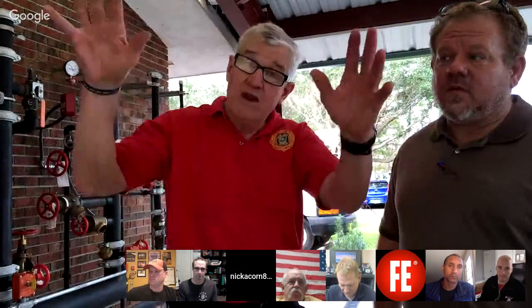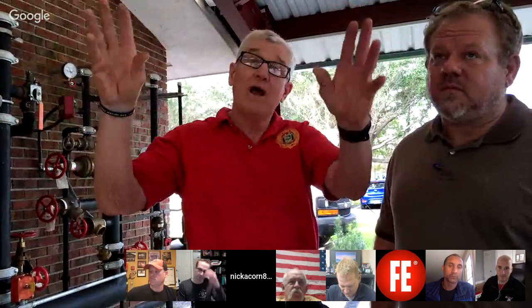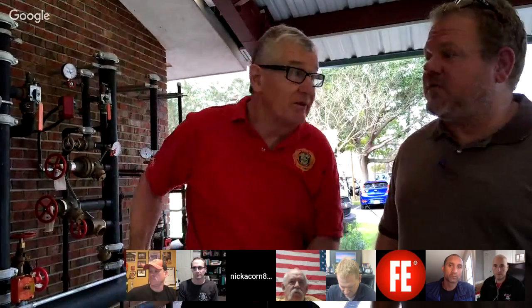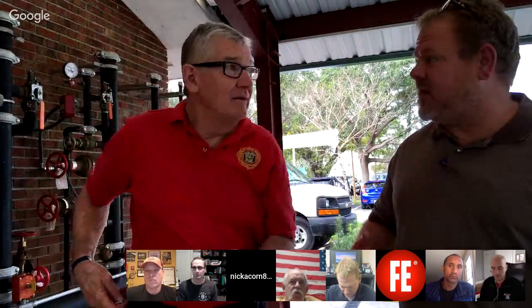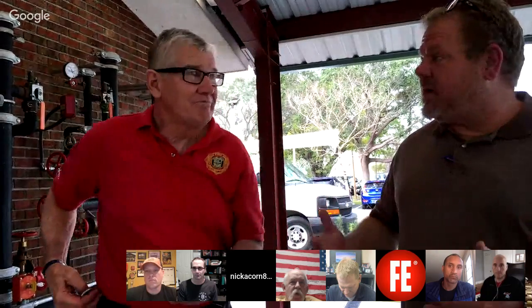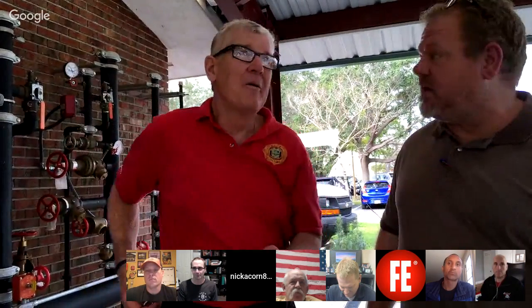Now, if it's going to be a two standpipe system, it's going to be 500 from one standpipe and 250 from the other. That's going to be three of the most hydraulically remote outlets. Why are the fire departments so scared to pump up these standpipes? If they're going to break, let them break in a training scenario, not in a fire scenario.